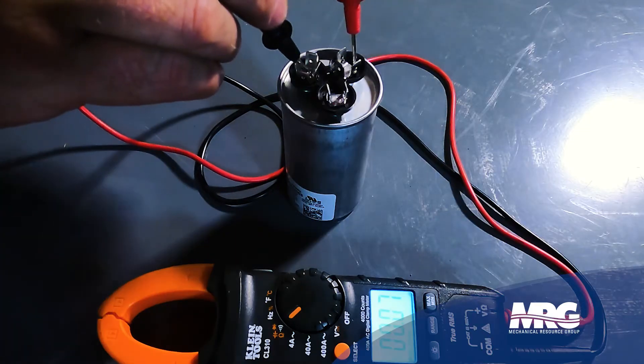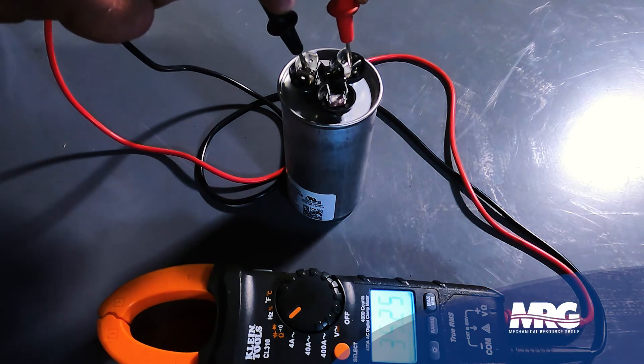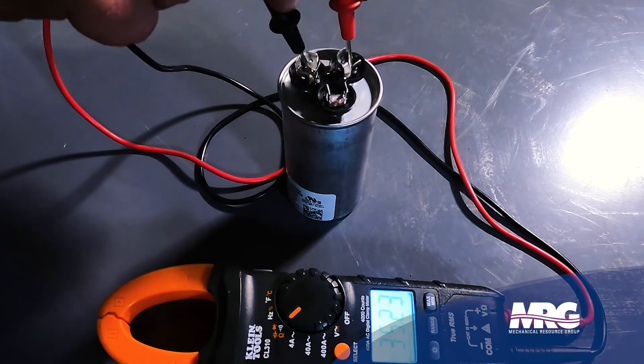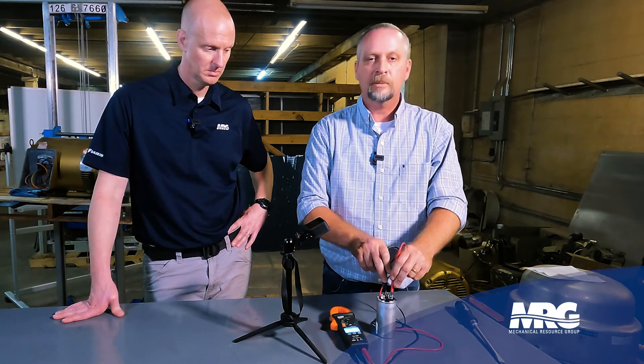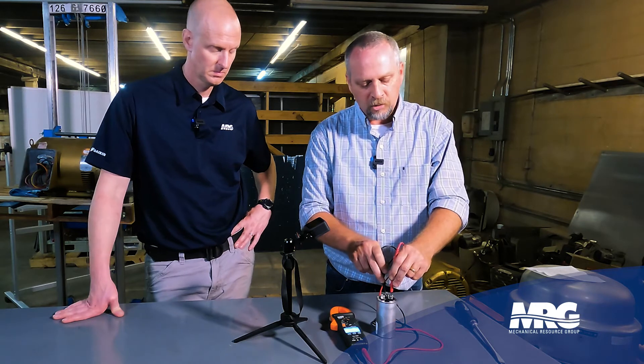Now I'll do the same procedure and check my compressor side — from common to compressor. Hold it down tightly for about five seconds. This is a 35 microfarad capacitor and it's reading 35.2 — that's good. If it was reading 32, that would be more than 5% — probably time to change that capacitor.